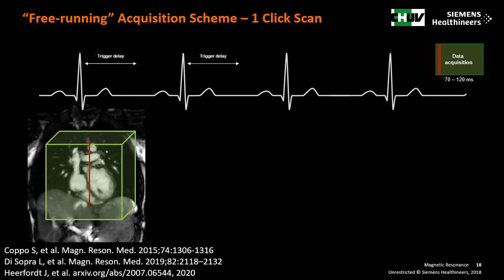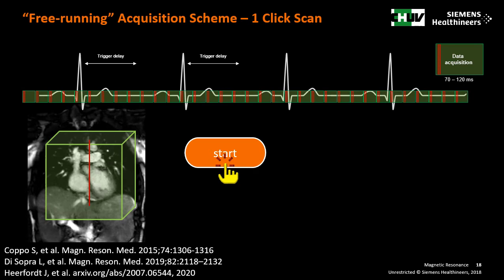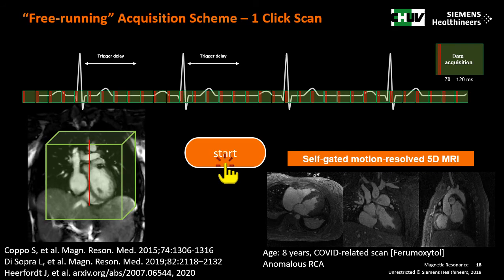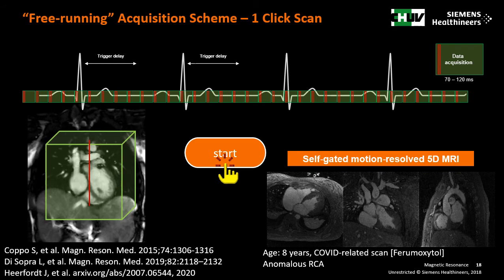In conclusion, we presented a way of performing coronary MRA in a single click. We have a cubic field of view, a one-click start, and continuous acquisition with no user interaction required. Two kinds of reconstructions are performed: a similarity-based anatomical one that happens at the scanner, and a self-gated motion-resolved 5D reconstruction from which cardiac function can be extracted.